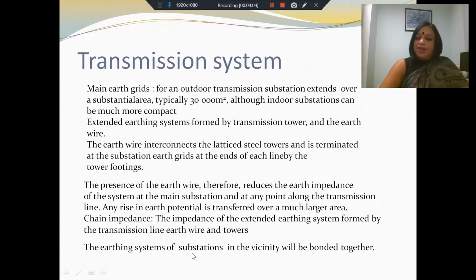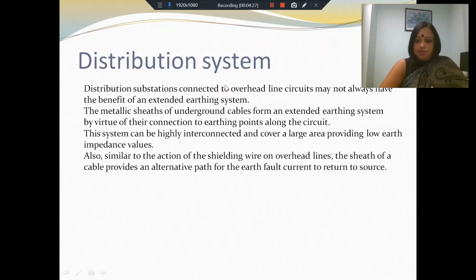This is true in the case of an outdoor transmission system. If you have an indoor substation, we don't have such a large area available. So the benefit of an extended earth system is somewhat less in the case of an indoor substation. If you look at distribution substations, they generally do not have these earth wires. They do not have the transmission lines. So therefore, the overhead lines in the distribution substation are not as well earthed as in a transmission substation.